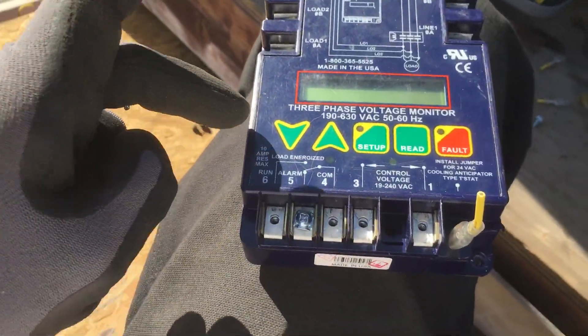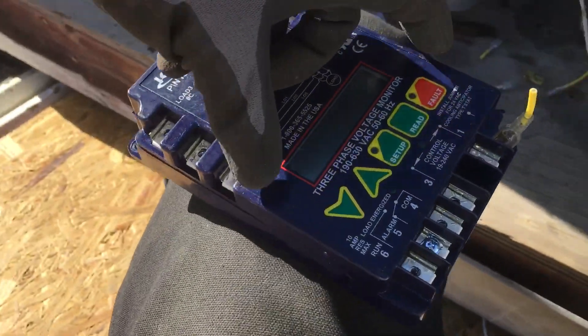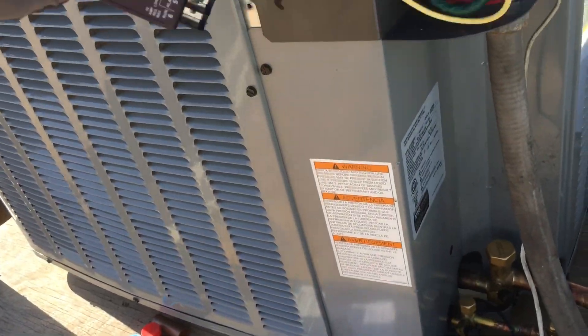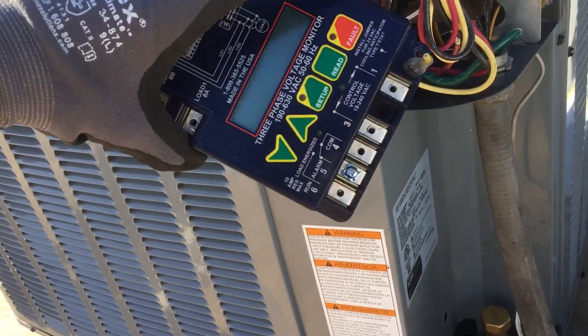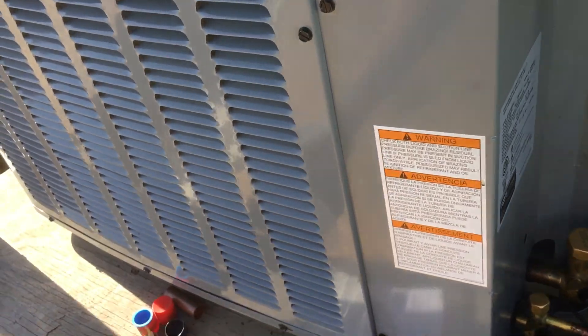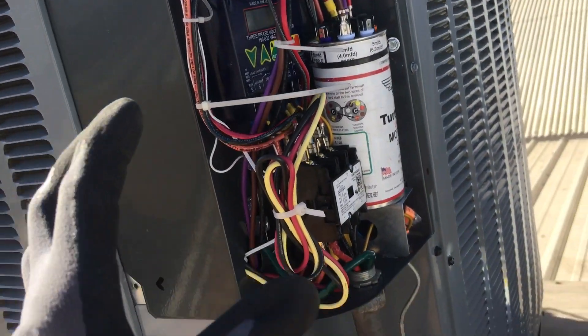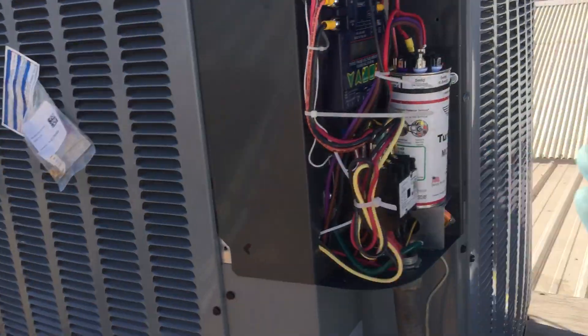What this unit was doing was intermittent faults. As you saw in my last video, all you had to do was touch the case right here — push on the case in the corner — and the vibration from the fan or the compressor would make the whole unit and all the lights turn off and on. That's working good now. All I did was swap it out.